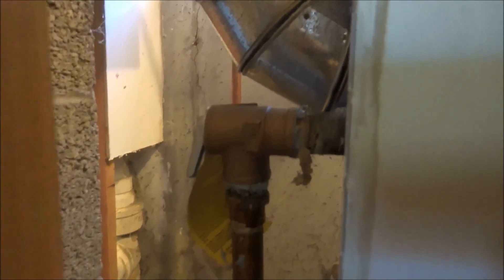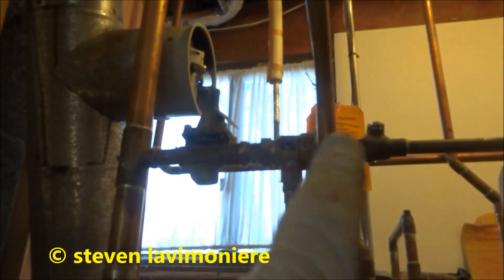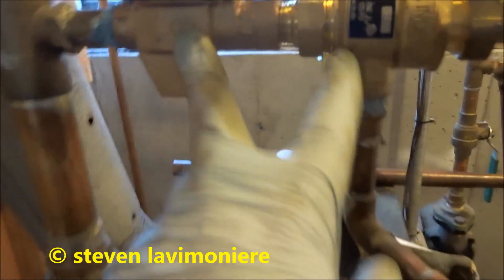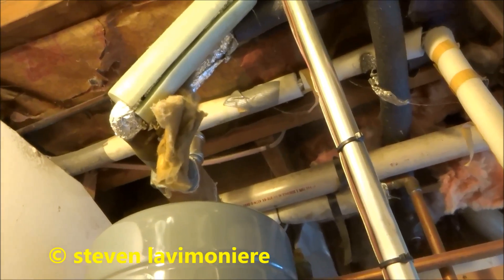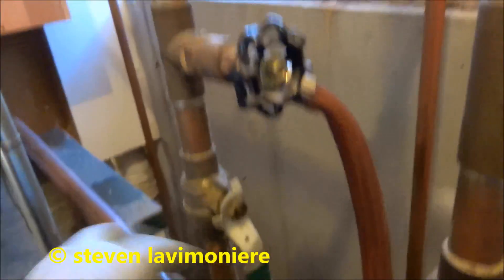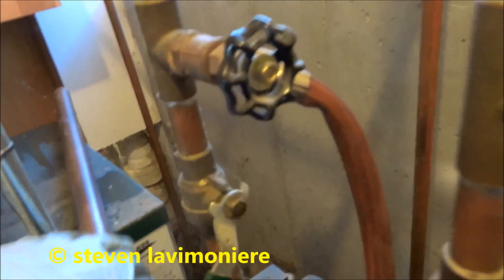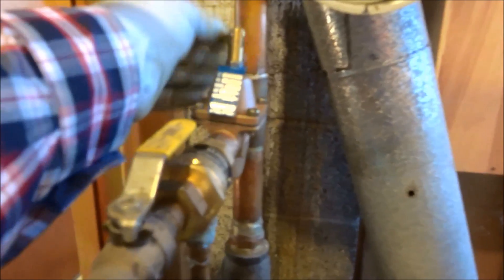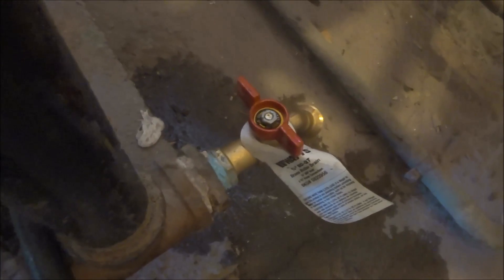I got the one off and I cut off the bottom. You can see it's kind of just corroded. Got the one in back there. Oil is all drained. Next I'll probably do this feeder, new feeder, new tank, high vent. The high vent here I'm going to purge it, get all the air out of the zones. I'm going to put a little boiler drain on there too.